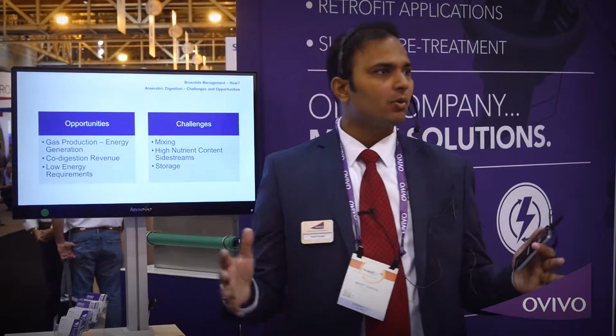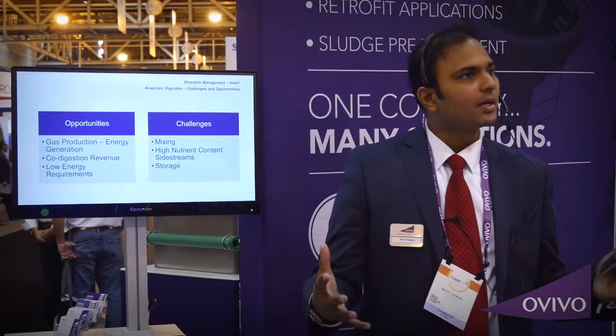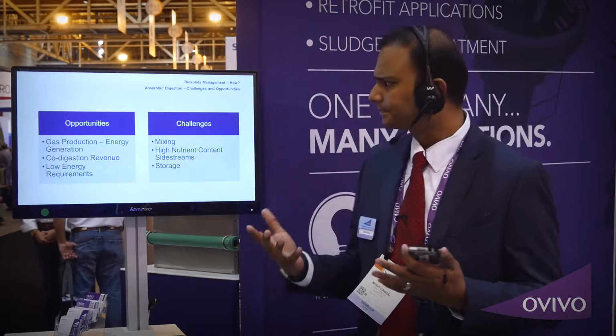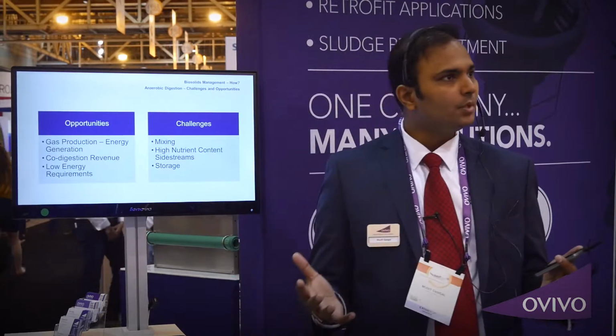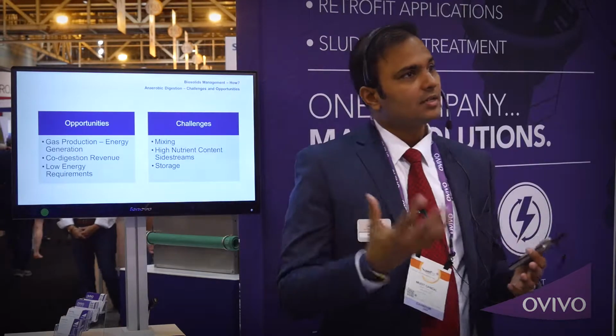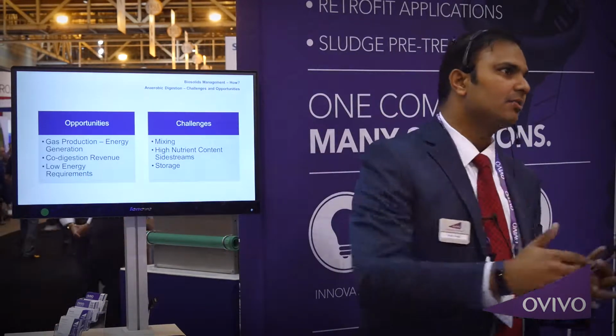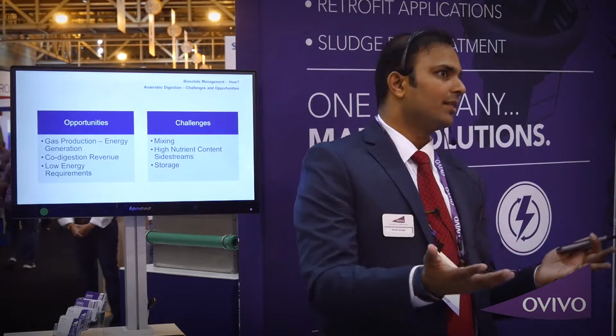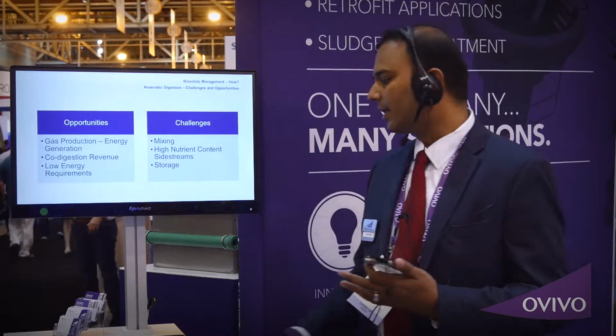And of course, the energy requirements are a lot lower because it's an anaerobic process, which is less energy intensive in general. However, it does present challenges. Mixing can be a challenge in these digesters to ensure all the bugs get the right amount of food. Anaerobic digestion does produce very high strength side streams, which are very concentrated in nitrogen and phosphorus, and so that does lead to problems of now trying to mitigate that additional nutrient load which is taken to the head of the plant. And of course, storage. So now you're producing biogas, which is a great thing, and now you also need to store it to be used at a later point. So there's different ways of going about that.